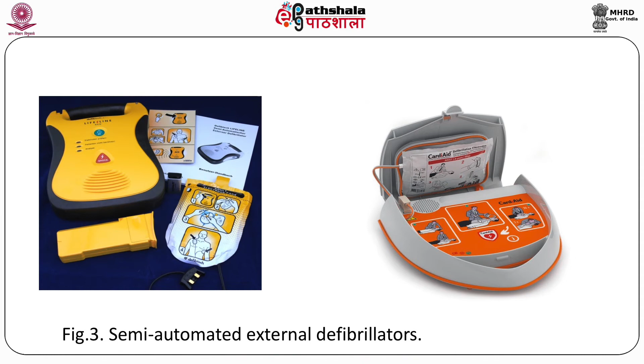In the event of sudden cardiac arrest, defibrillation has to be coordinated with high quality CPR. The chest is exposed, optimal size paddles or patches are selected and positioned appropriately. Turn on the power to the defibrillator and verify the presence of a shockable rhythm. Select an appropriate energy level and deliver the shock as per the need after making sure that all are clear of the patient. There should not be any oxygen flow over the patient's chest for fear of possible ignition.